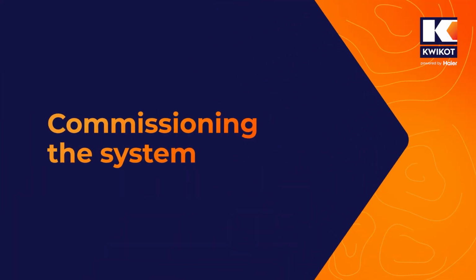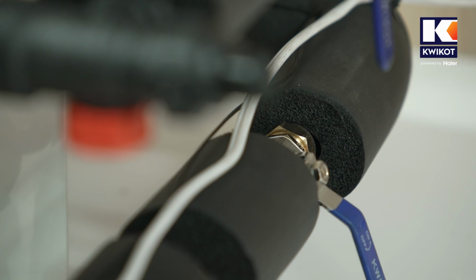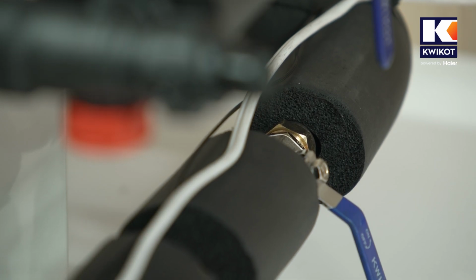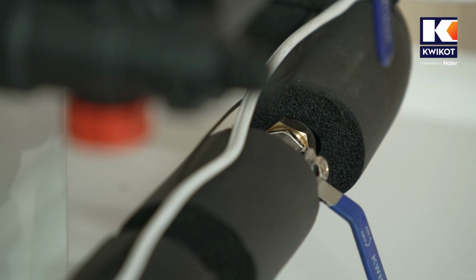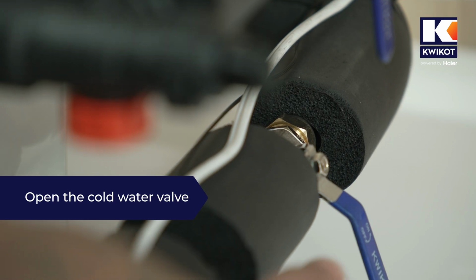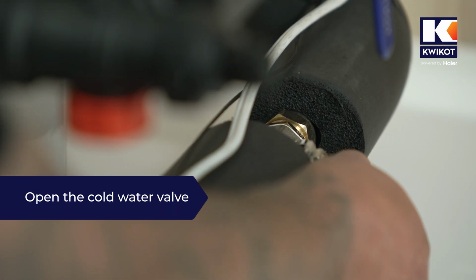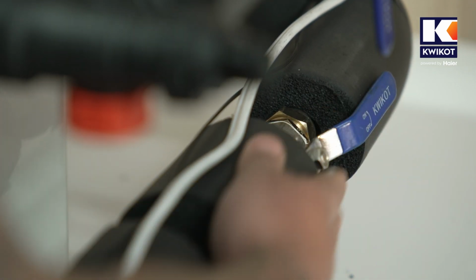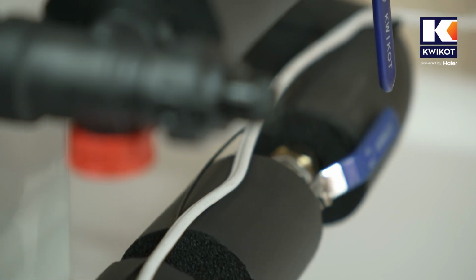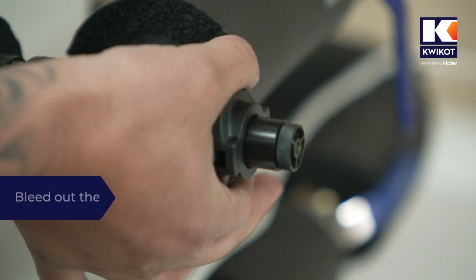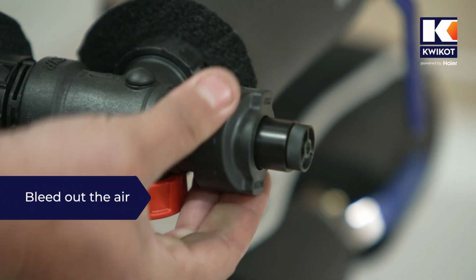Commissioning the system. Our pipework and electrical connections are complete, so we can now commission the system. First, we open the bottom lever valve on the inlet pipework. The cold water will flow through it and then through the heat pump's heat exchanger.